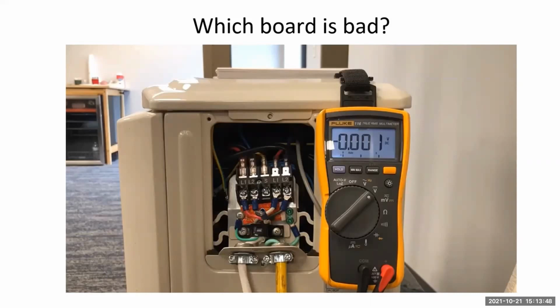You want to put your L2 for your red lead and the S terminal for the black lead on the outdoor unit. And you're going to be reading DC volts. You want to see negative DC volts with a little bit of pulsating. If you do not see any negative DC volts with pulsating at the S terminal, then more than likely your outdoor board is bad. So then you're going to switch over and you're going to leave your red lead on L2. You're going to move your black lead to the S wire that comes from the indoor unit. And you're going to check for pulsating DC volts there. If you do not see any positive DC volts pulsating from the indoor unit, then that board is bad.